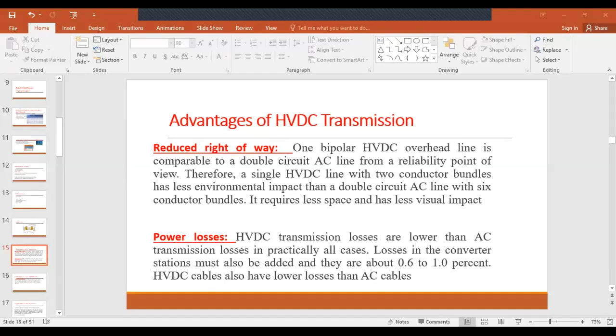Then the second one is power losses. Actually, the main purpose is to increase the power and reduce the power losses. So, how is DC saving our power? High voltage DC transmission losses are lower than AC transmission losses in practically all cases. We can understand it from some basic concepts: AC resistance is more than DC resistance, and we know that V equals IR. So when the resistance is higher, the drop would be higher. At the same time, in AC we have reactances as well, which are not present in a DC system. So the reactances reduce, the resistances reduce, and as a result, the power loss reduces. So this is the second advantage of DC over AC.